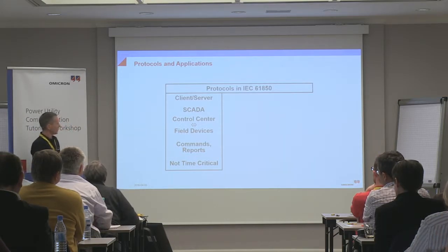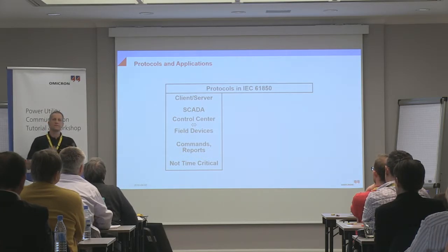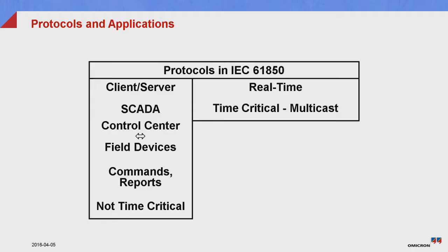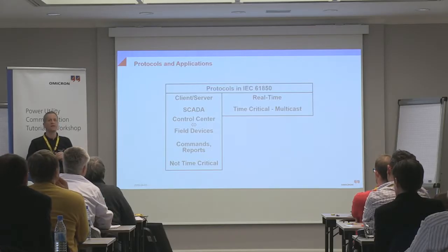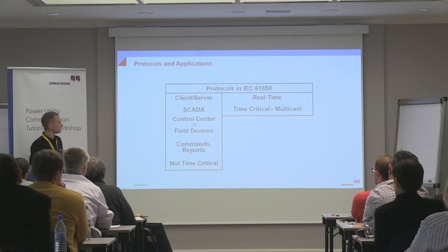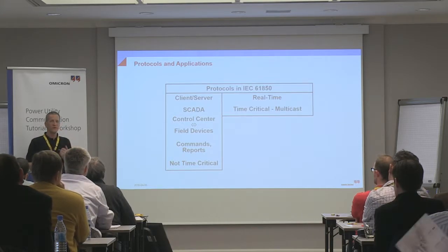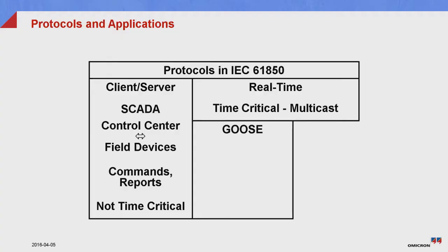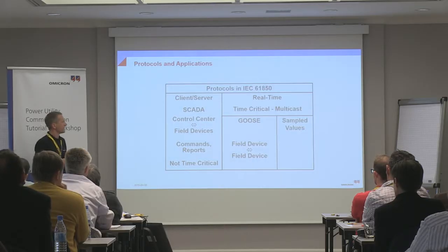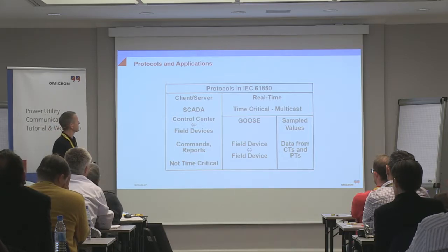Here we have a communication which uses commands which are then also confirmed. On the other side, we have these real-time protocols. This is time critical. You heard about the multicast mechanism behind that. Because this is very performant, we're using this. There we have on the one hand the GOOSE protocol between the field devices, and the sampled values as the data from CTs and PTs.